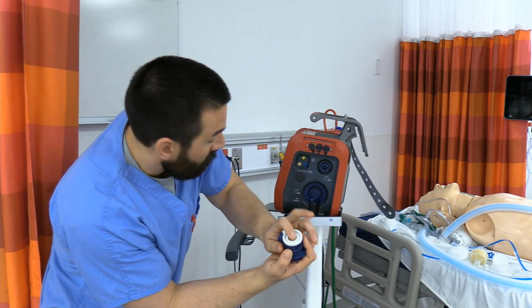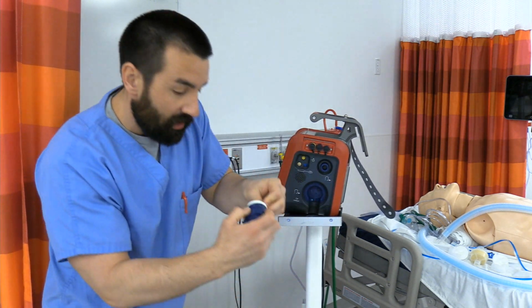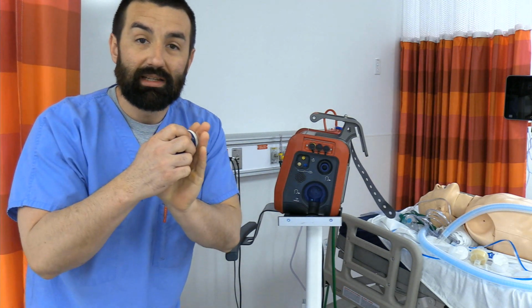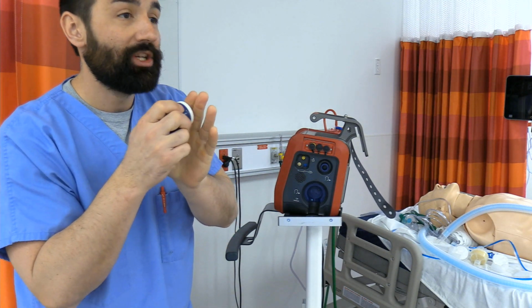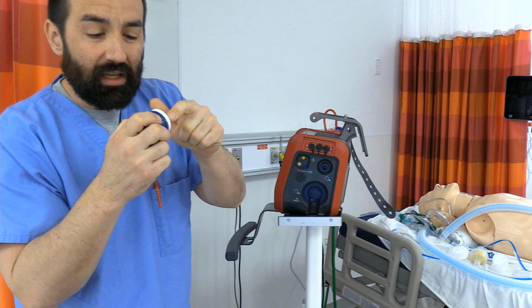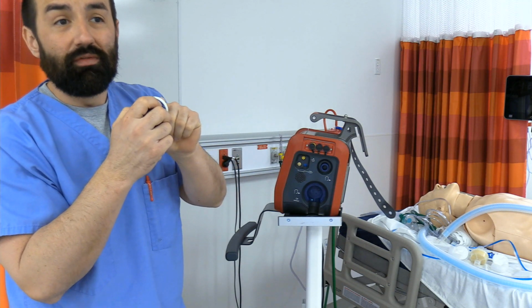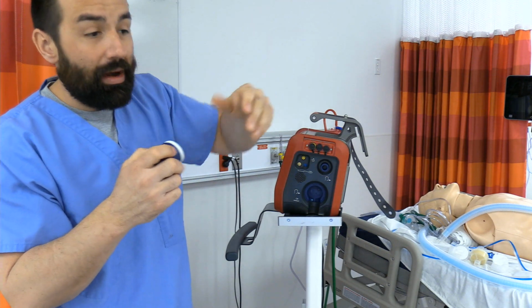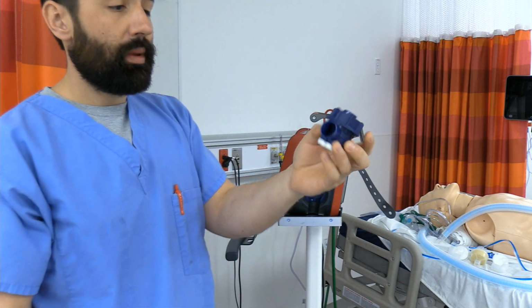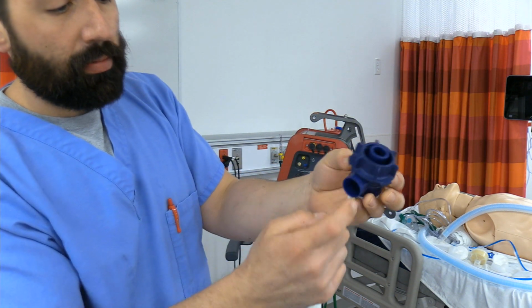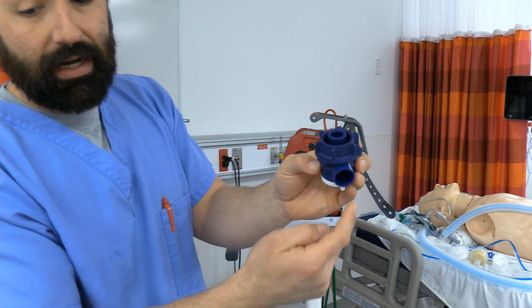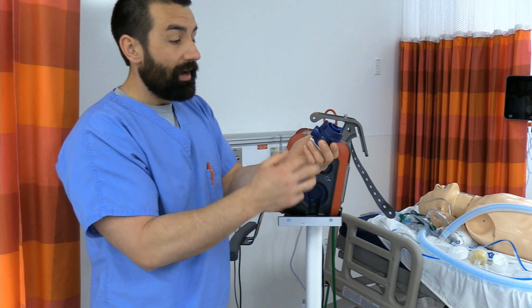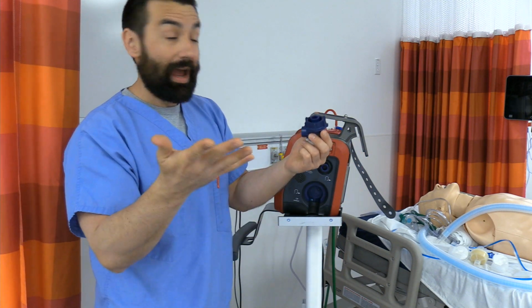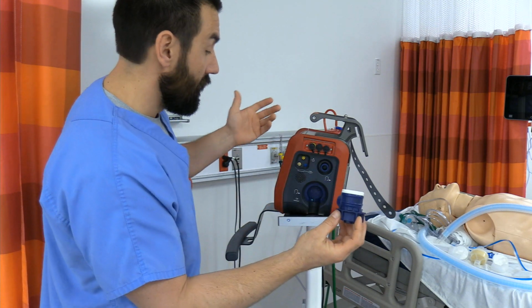That little metal right there, ultimately, there's going to be contact made on this to close that exhalatory valve when we're trying to deliver gas to the patient. In between breaths, it's going to keep enough appropriate tension on that exhalation valve, combined with the bias flow, to maintain our levels of PEEP. Our connection is going to hook up right here, and then this bigger port is not a standard respiratory fitting. That is essentially the exhaust port, where all that gas is going to be exhaled into the ambient atmosphere.